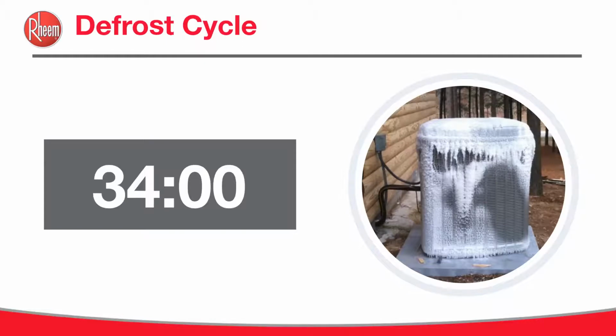So three things are required to initiate defrost. The outdoor temperature must be below 35 degrees. The compressor must have operated for 34 minutes with outdoor air temperature below 35 degrees. The temperature differential between the outdoor temperature and the condenser coil temperature must exceed the board algorithm.